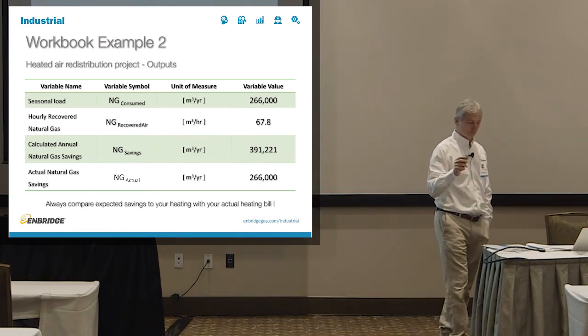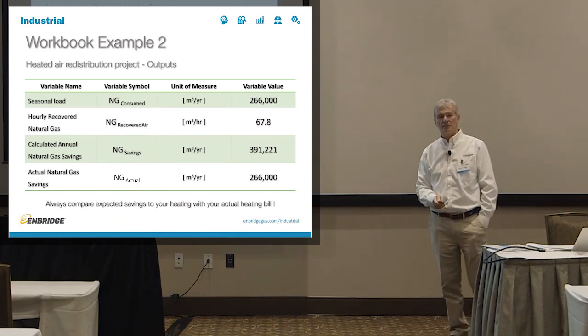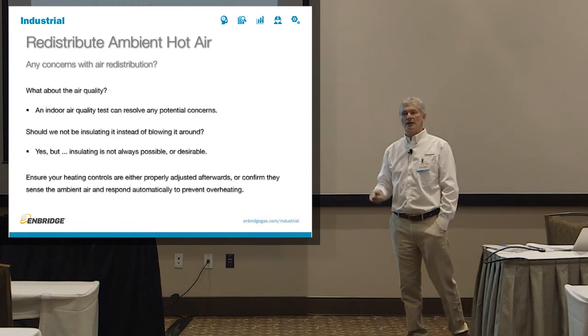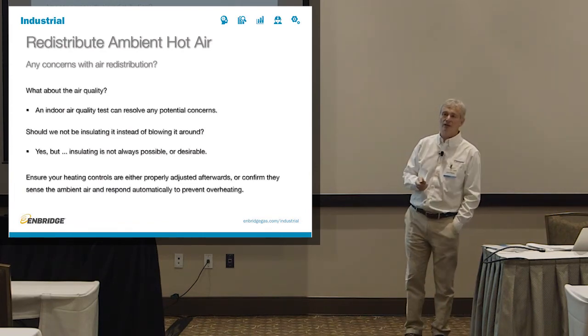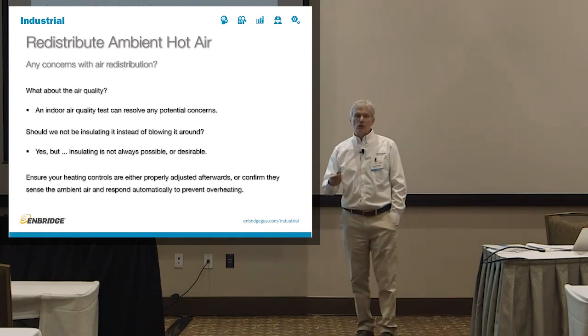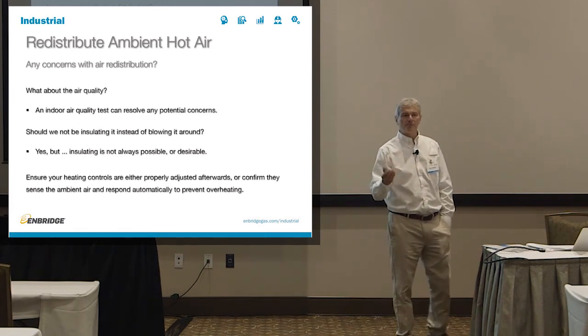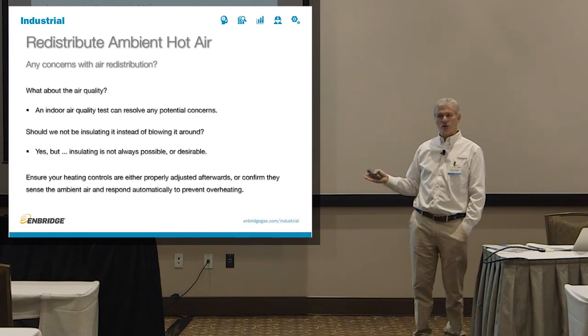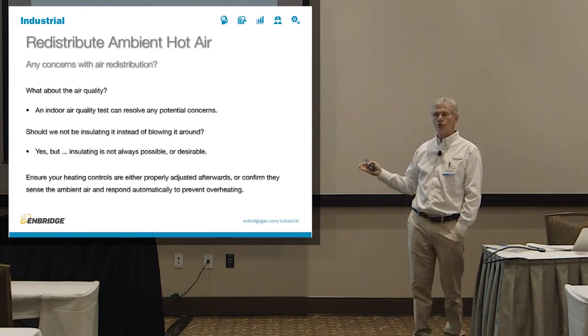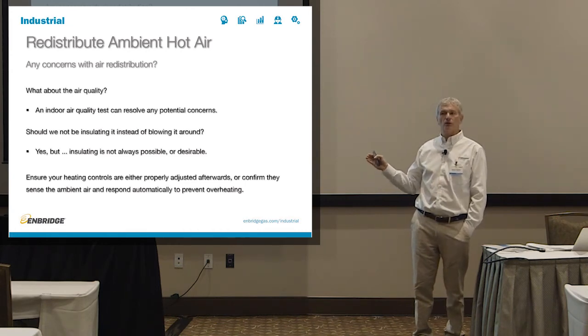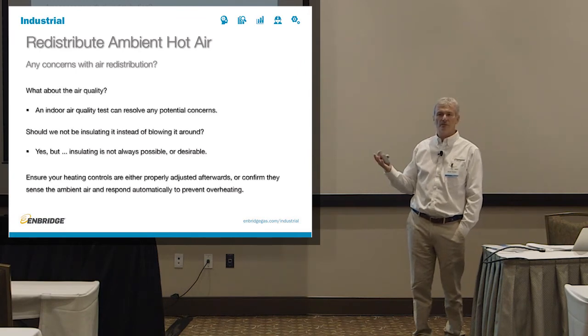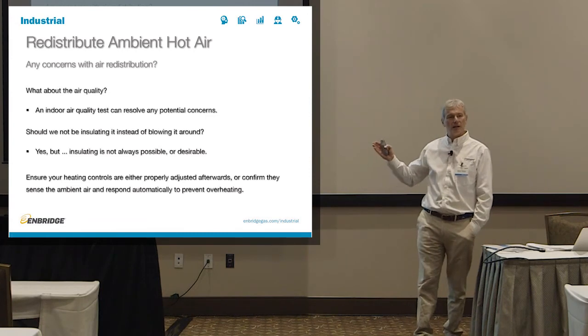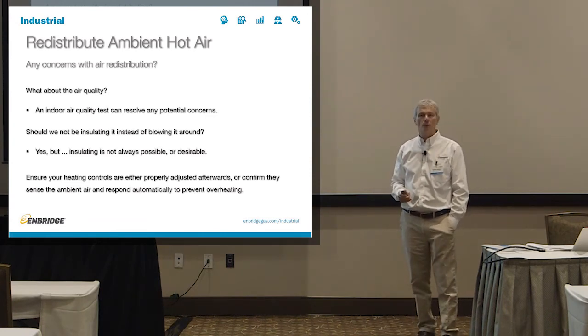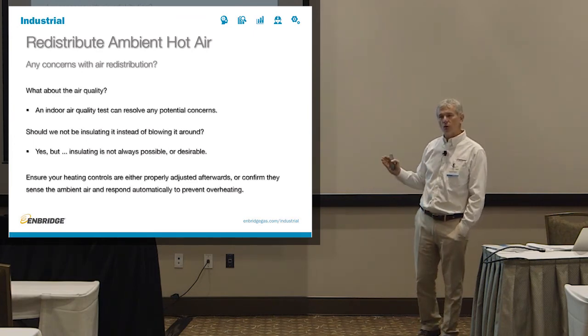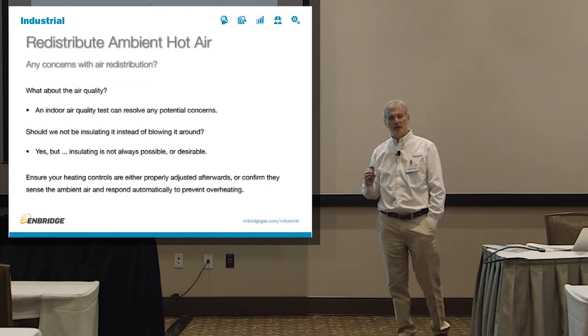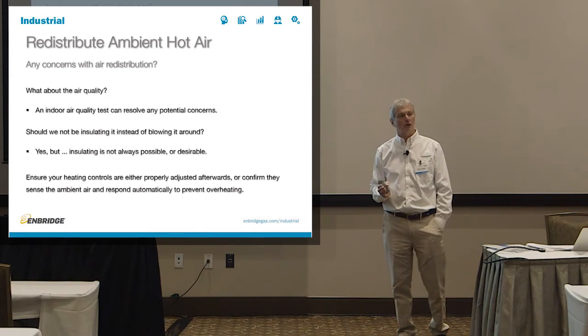So we'll go back to a question that pops up almost always when we talk about air redistribution. Are there any concerns with the air quality? Everybody's always concerned, can we just blow this air around? So if you're really concerned about air quality and that's the only thing that's really stopping you from implementing an idea like this, and it's worth your while because you calculated and the savings are sufficient to make an effort to do it, I would always suggest doing an air quality test if that's your concern. Air quality tests these days can probably be had for $1,000 or something like that. It's well worth the effort, and it goes into your payback, and the payback will still be below a year for most of you. So that's the only concern I would have, the air quality. And again, in a very, very high majority of the cases, that is never going to be a problem at all.